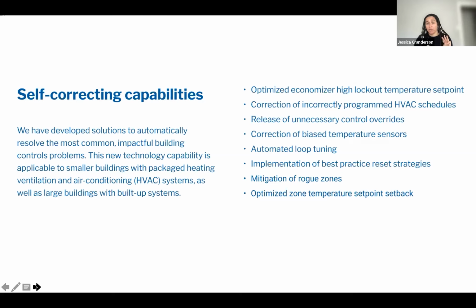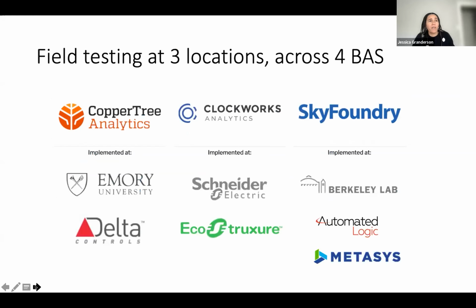I'm going to show 3 examples from the field on automated loop tuning, implementation of best practice reset strategies, and suppression of rogue zones. And we've also looked at implementing zone temperature set point setbacks in an optimal manner. We've made it through several rounds of iterative field testing, actually across 5 different building automation systems at this point since I created this deck. So we've done this at Emory University with Delta and Siemens Systems, at Schneider Electric's headquarters with Schneider EcoStruxure, and at Berkeley Lab on Automated Logic and JCI Metasys systems.